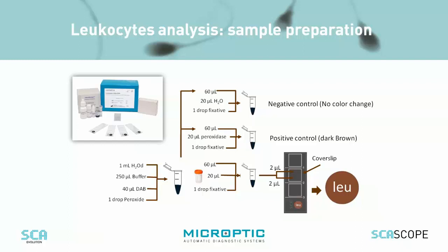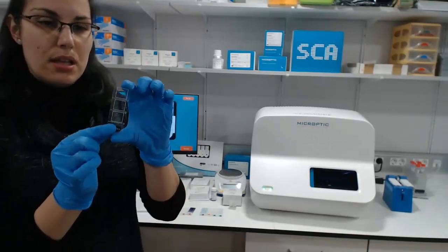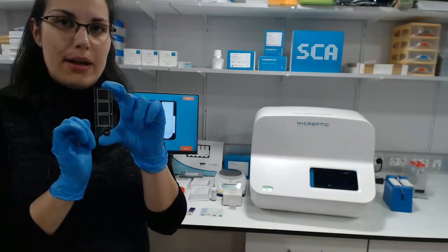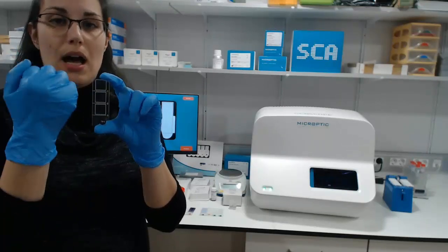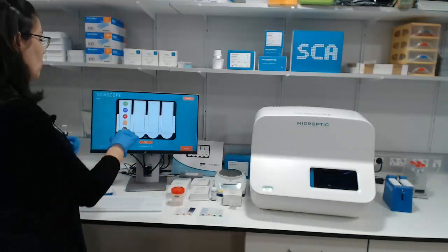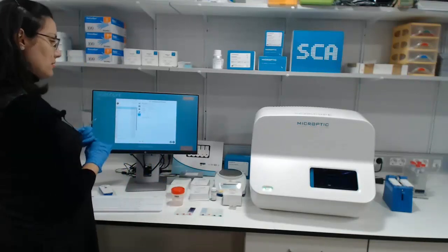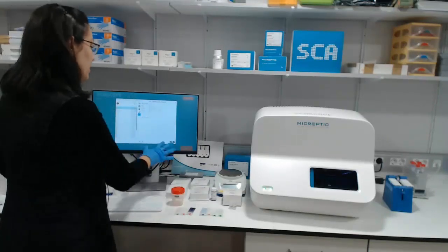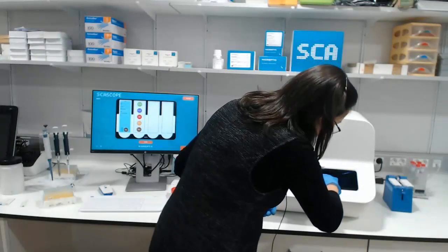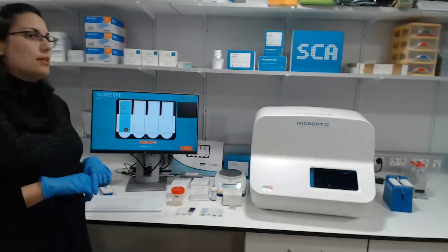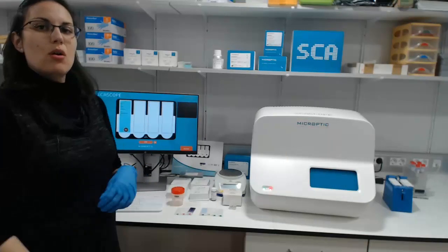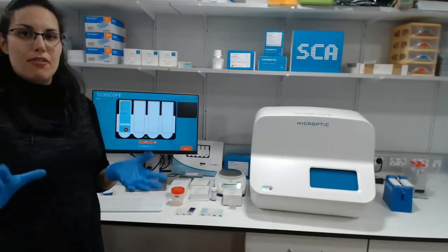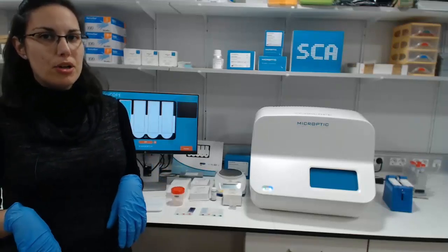Once the negative and positive controls are checked, we can mix this substrate with our semen sample and take two small drops and put them on an analysis area. The kit includes slides with three analysis areas, and you can choose one and load it in order to analyze it. We will select the patient, the reference, and introduce the area to analyze — for instance, area one — then locate the sample in the holder of the SCA scope and start the analysis. The system will capture 100 fields and classify all these types of cells captured.